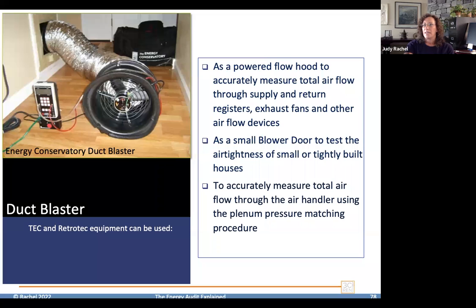The duct testers from both companies are interesting because they're multifunctional. They can be used as powered flow hoods. They can be used in extremely tight houses as the blower door fan. So instead of the bigger fan for the blower door, you use the duct testing fans for your blower door in tight houses, such as a passive house. And they can also be used to measure total system airflow. So not only the leakage of the whole system, but they can actually tell you what the total system airflow is when you set them up for that test.